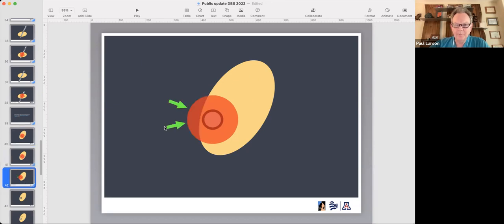Let's say though that the position is a little bit off to one side. We're still in the target, but when we turn this electrode on, we're spreading this red area of stimulation outside the intended area, this orange thing. So these green arrows are electrical current or stimulation that's going outside of the intended target. And that can cause side effects. It can cause speech troubles, for example, or it might cause a little bit of tingling, as we talked about earlier.